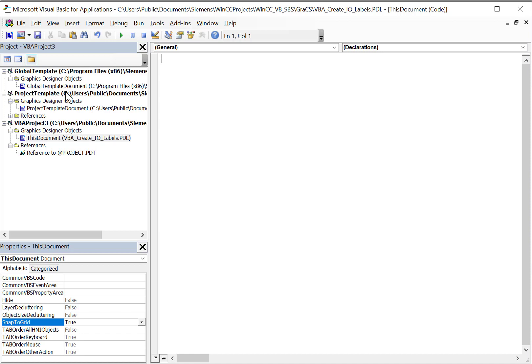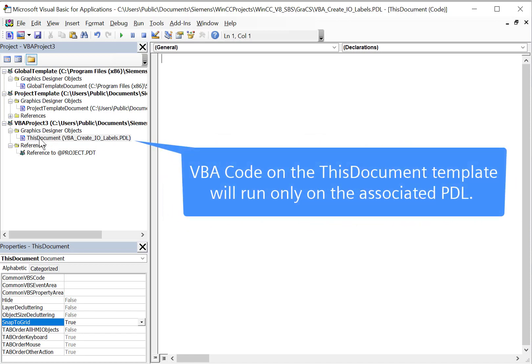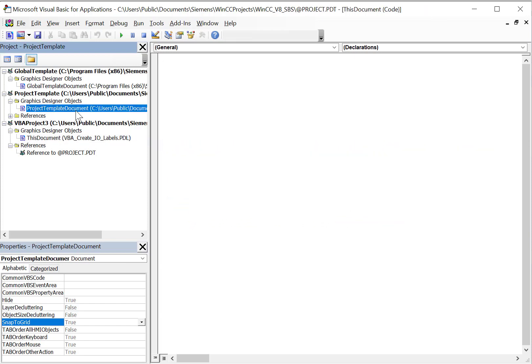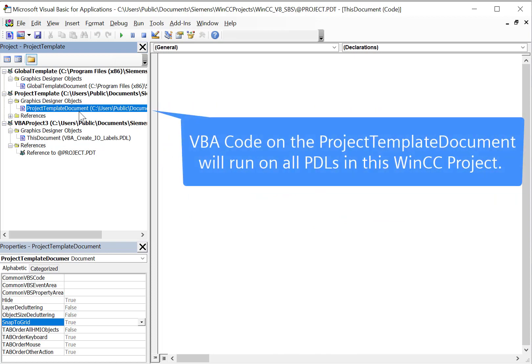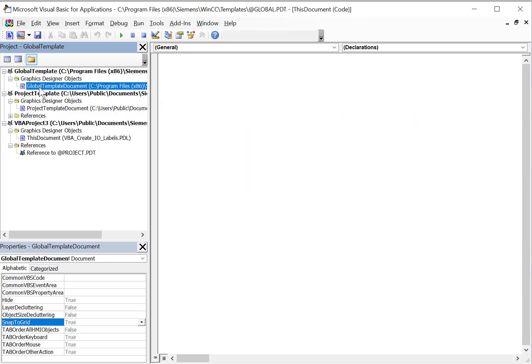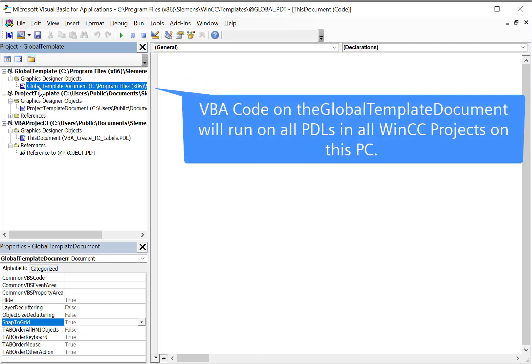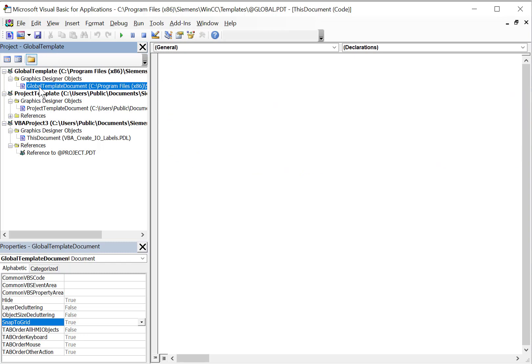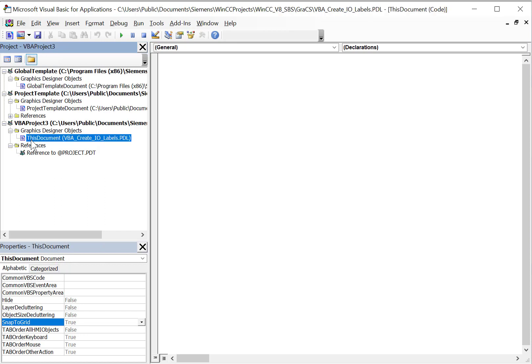You'll notice there are three different templates. We have a template for the individual document you're on, so code written here will only work on this particular page. Then we have a project template document, meaning the VBA will be available to any Graphics Designer document in this project. Finally, we have the global template document, applicable to any WinCC project on this computer — so if you're making design tools in VBA that you want to use across different projects, you would put your code there. For now, I'm just going to put it on this document.